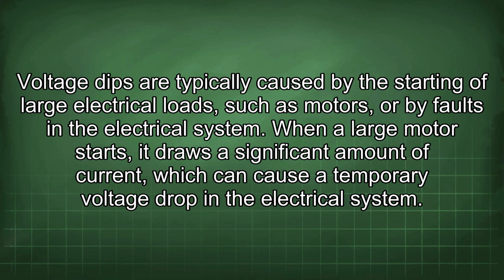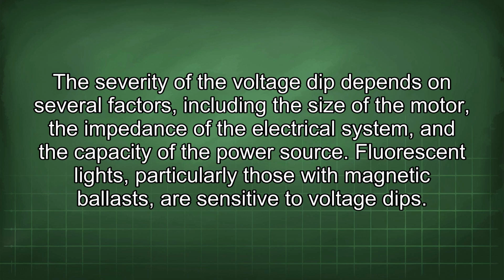Voltage dips are typically caused by the starting of large electrical loads, such as motors, or by faults in the electrical system. When a large motor starts, it draws a significant amount of current, which can cause a temporary voltage drop in the electrical system. The severity of the voltage dip depends on several factors, including the size of the motor, the impedance of the electrical system, and the capacity of the power source.